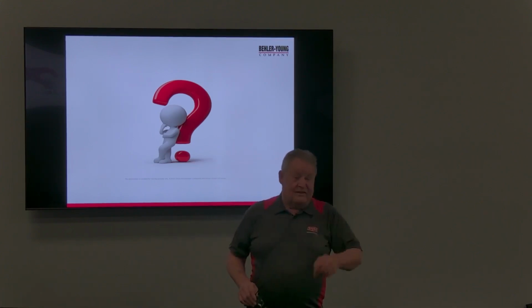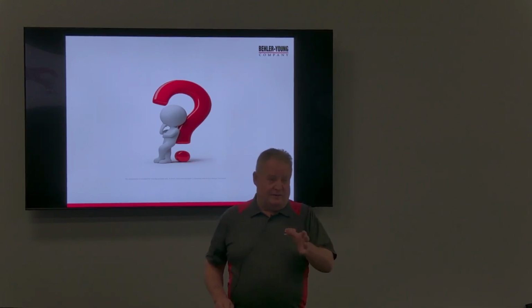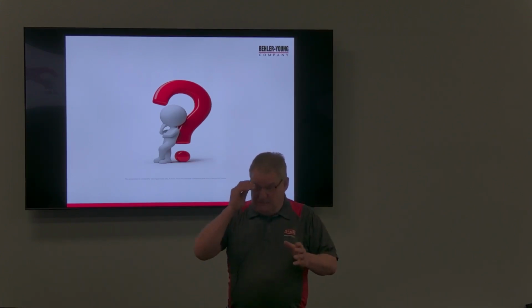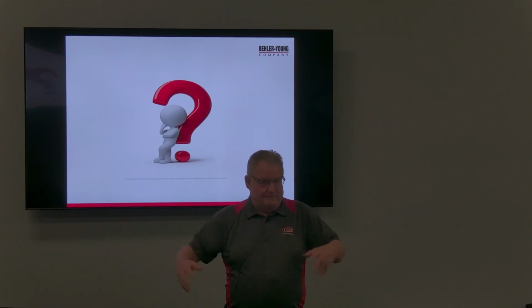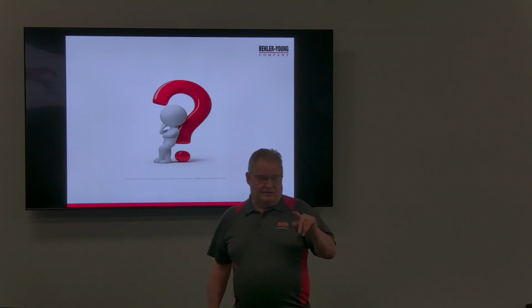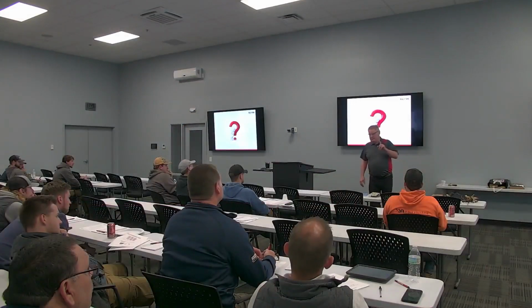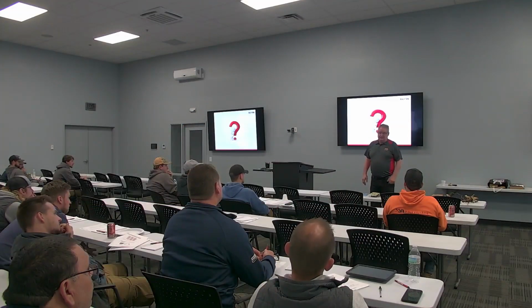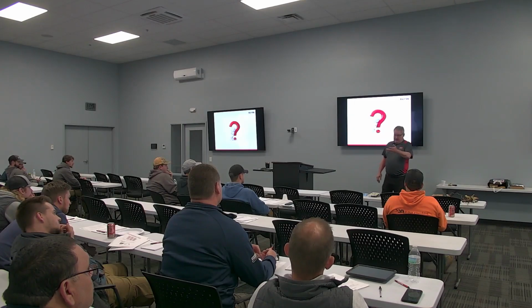The last I saw, I saw a thing where they did 454B, they recharged, and everybody know what I mean by that? Your system is 50% low, you don't take it out, you just add new. And out of 8 recharges, they had a 1 degree temperature difference. So yes, you can top off the charge in 454B. R32 is not a blend because it's not a 400, so that won't be a problem either.